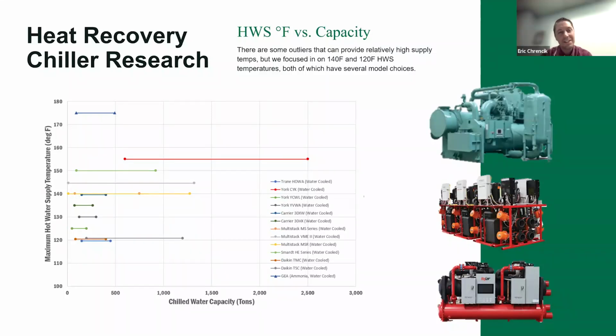York YK machines, the 400-ton model can get you 170 degrees, and then between 600 tons and like 1,000 to 1,200, you can only get 155. And then once you pop over 1,500 tons, you can get back to 170 again. So there are little things like that that are quite odd. And it just is what it is, from what I get from York when I talk to them about it. That's what the machines can do, and that's what they've tested and proven out.